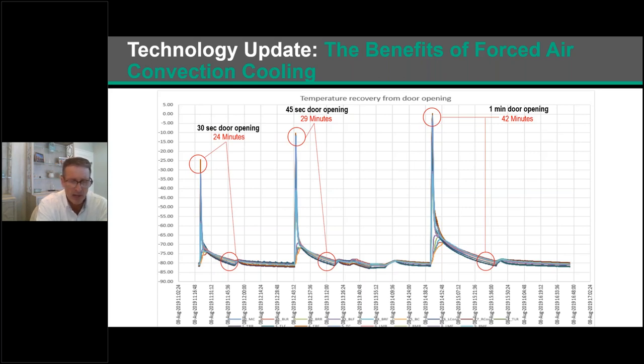So I'd also like to mention that the FARRAR minus 80 is equipped with what we call a dual primary refrigeration system. Some of you may know this as a lead lag assist refrigeration system. It's a familiar term used in the industry. This means double the refrigeration capacity to help you pull down from ambient down to minus 80. It also offers faster temperature recovery from door opening, and the freezer can maintain a control set point of minus 80, even with one refrigeration system. So the dual system is only for additional refrigeration capability, right? So therefore, the forced air solution presented provides a wider range of temperature control from minus 20 to minus 80, full redundancy, and as mentioned before, plus or minus 3 degrees C with an empty chamber. So the solution for better temperature uniformity and faster temperature recovery from door opening is forced air cooling, because again, the data tells the story. Next slide, please.